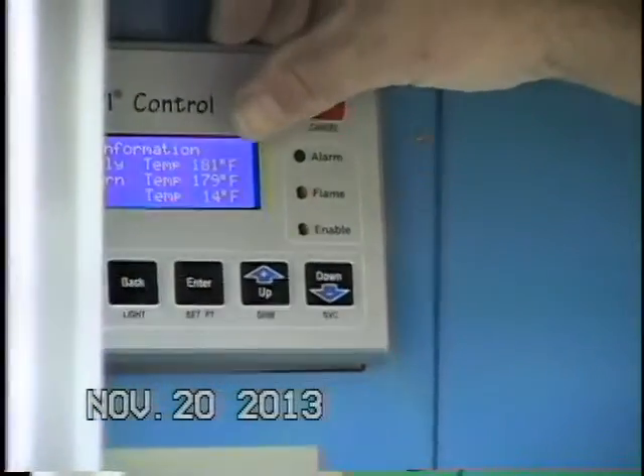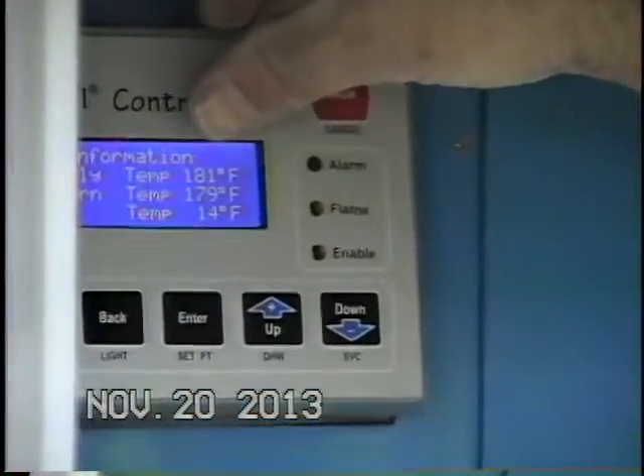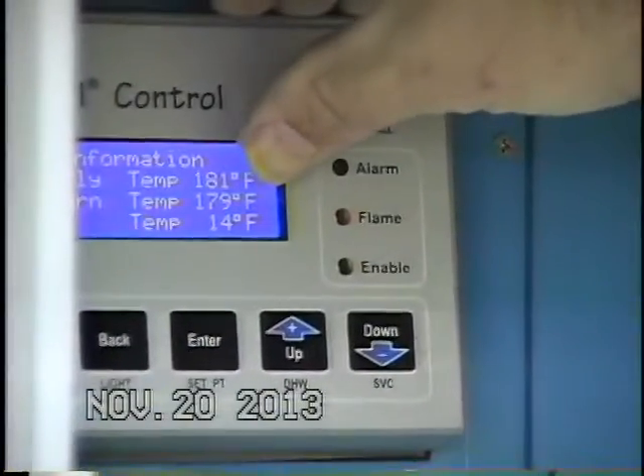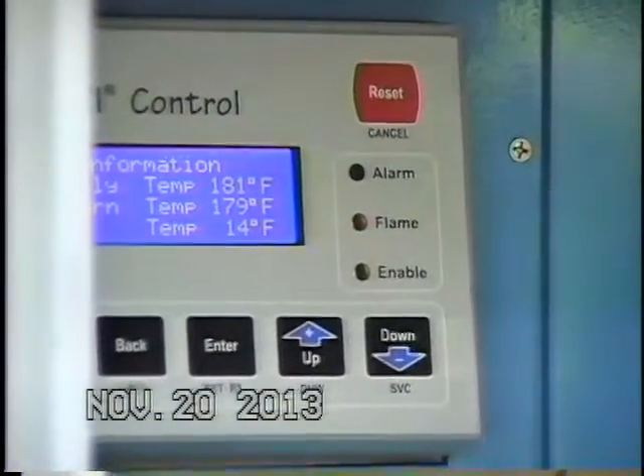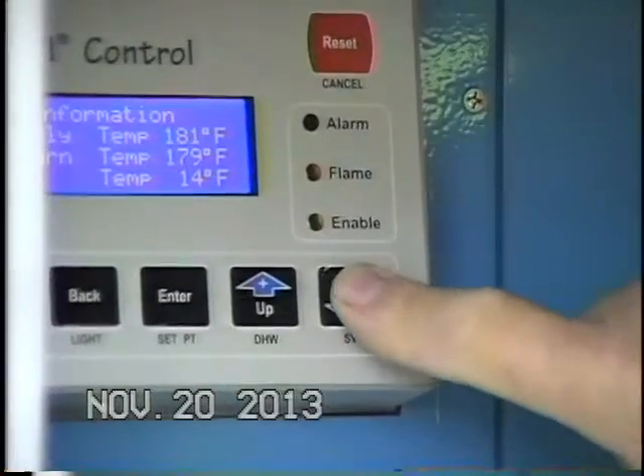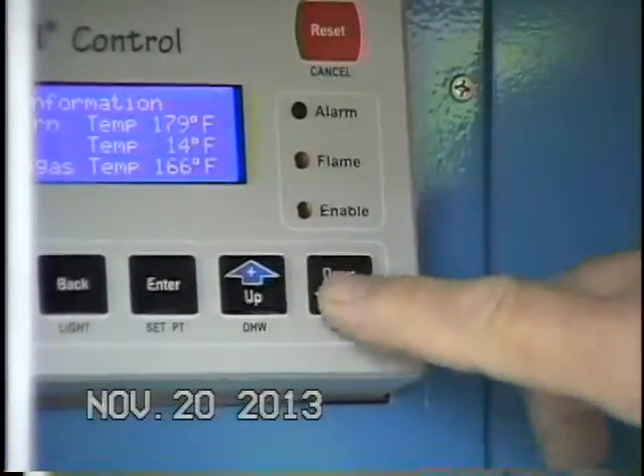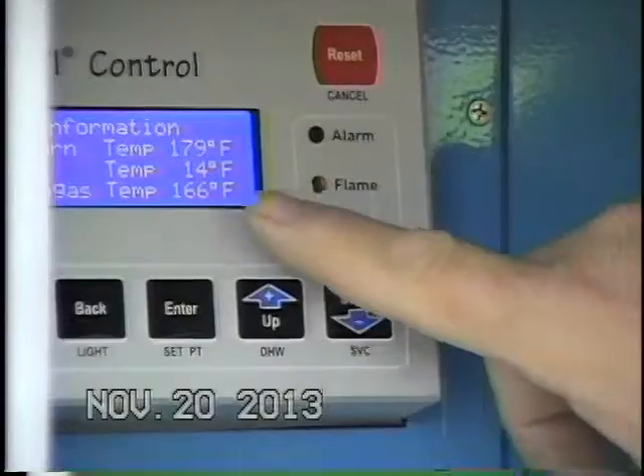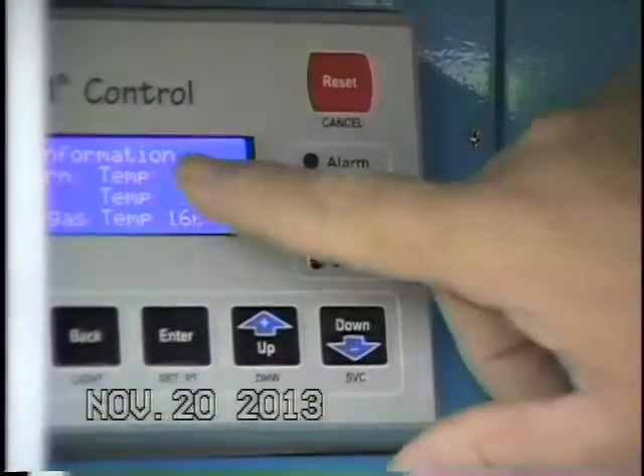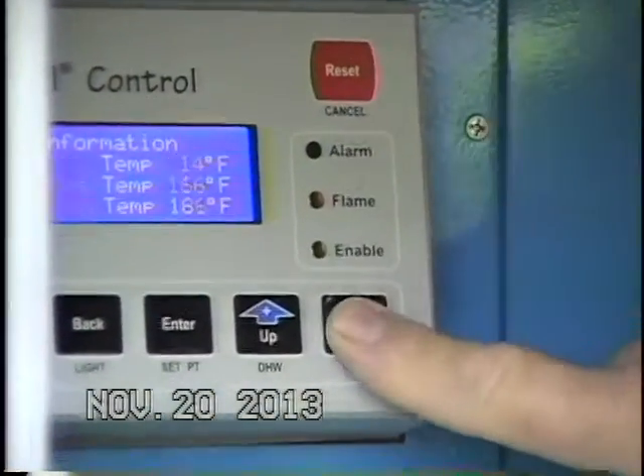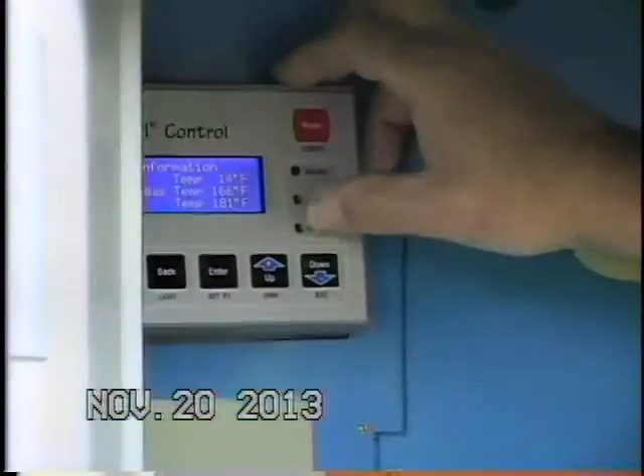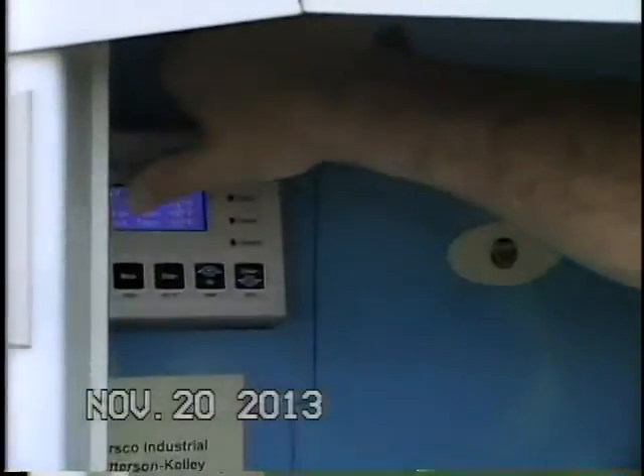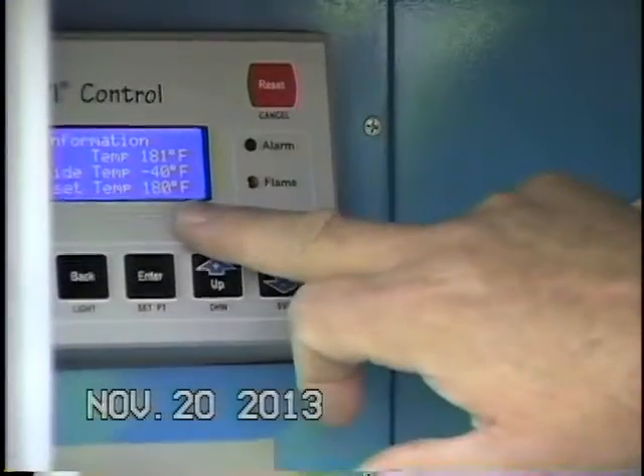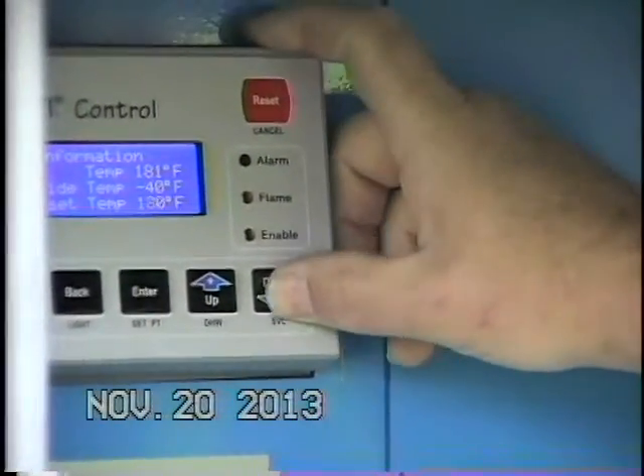And this is telling us our supply right now is 181. Our return is 179, so that means we're not pulling much heat out of it at all. And if you go down, it gives you flue temp. It gives you that. Ignore that. That's for domestic water. So that's why it just says 14 because it's not used. Outside air is not used. Right now its set point is 180. So that's the set point they're trying to hold in the system.